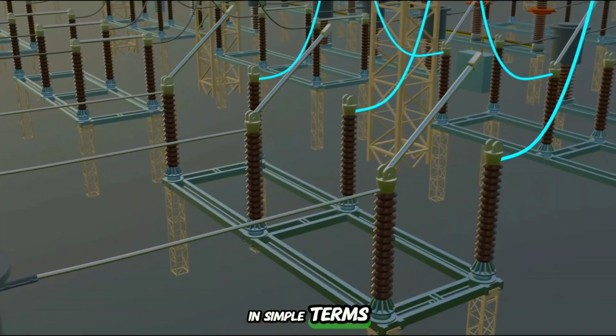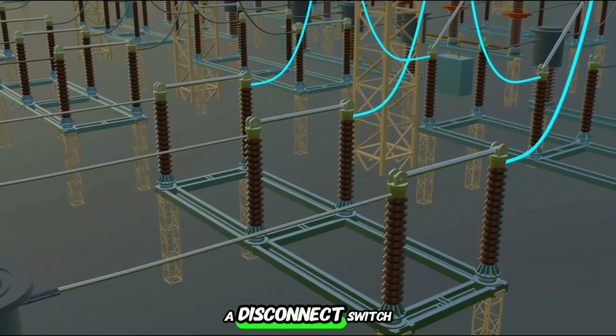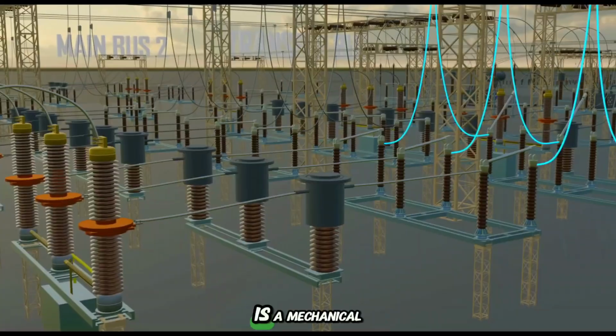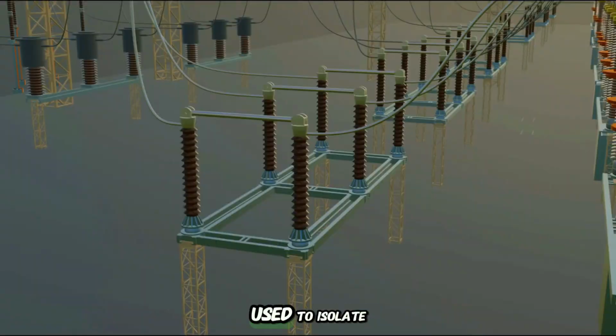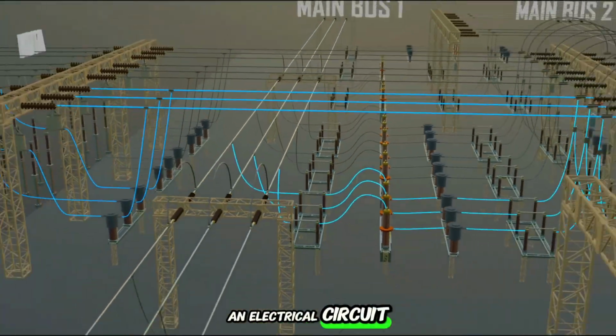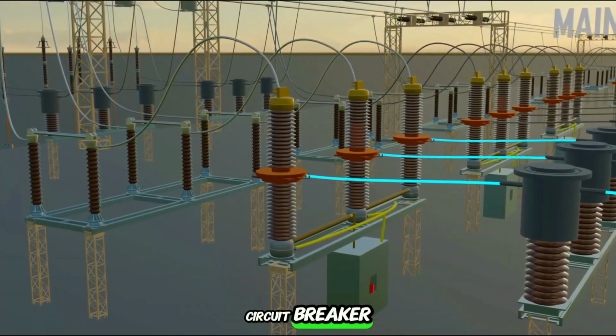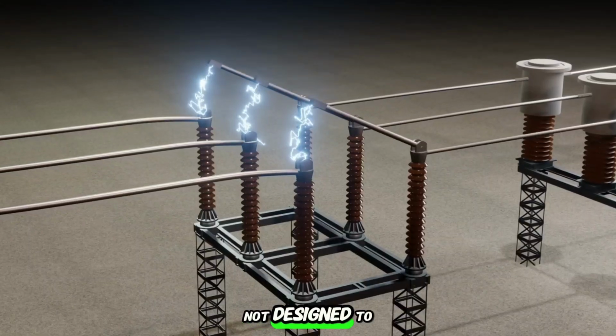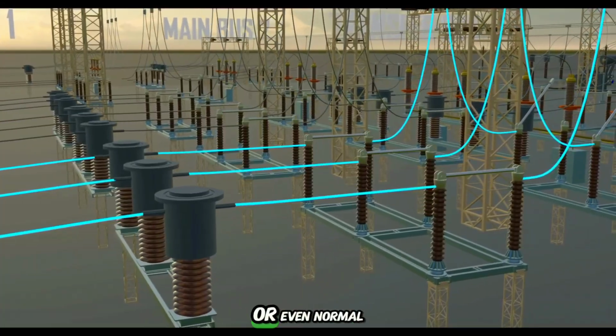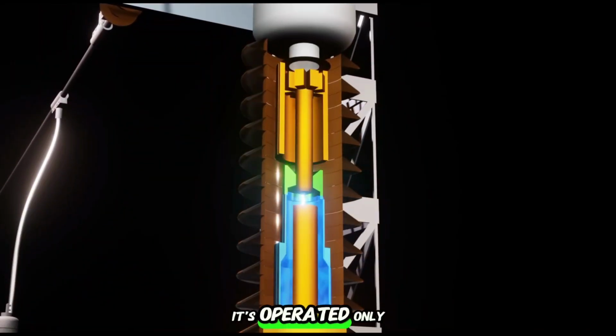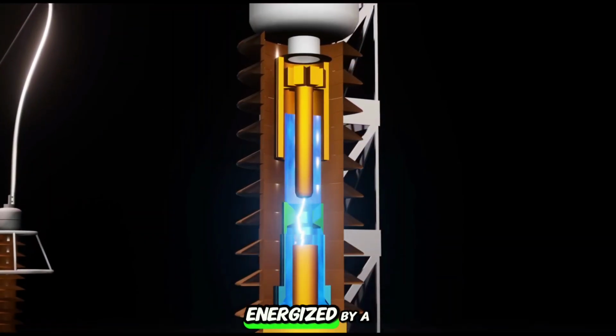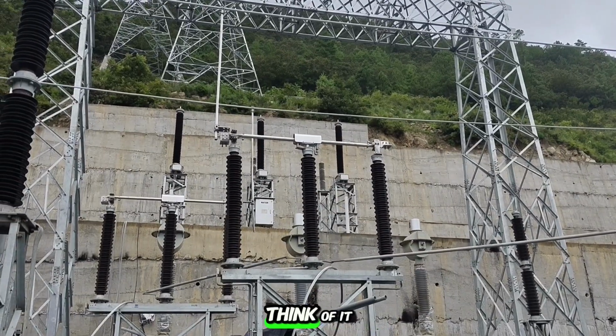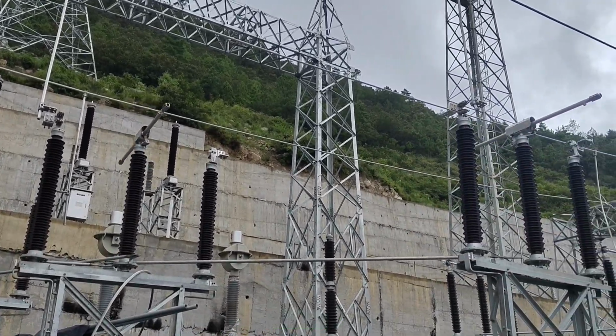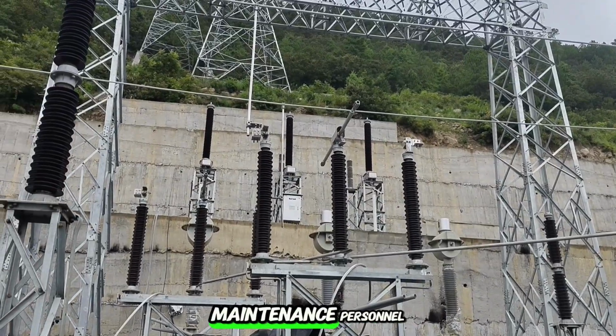In simple terms, an isolator, also known as a disconnect switch or disconnector, is a mechanical switching device used to isolate a section of an electrical circuit. Crucially, unlike a circuit breaker, an isolator is not designed to interrupt fault currents or even normal load currents. It's operated only when the circuit is already de-energized by a circuit breaker. Think of it as a visible break in the circuit, providing a safe working clearance for maintenance personnel.